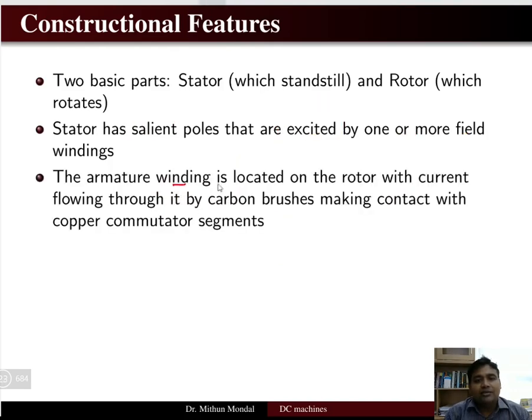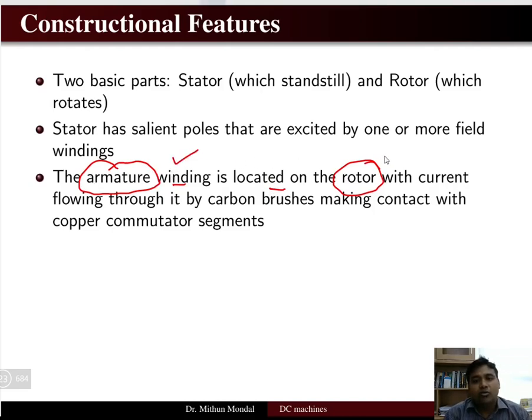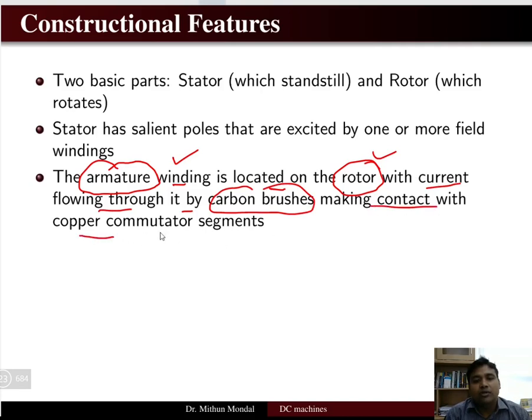The armature winding is located on the rotor, so 'rotor' and 'armature' are used interchangeably in DC machines. Current flows through the armature winding by carbon brushes making contact with the copper commutator segments. The current is tapped from the carbon brushes and is produced in the armature winding placed in the rotor.